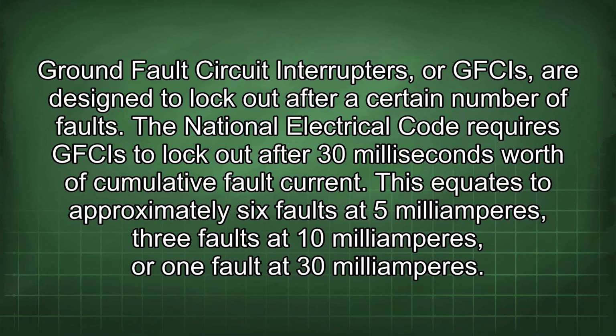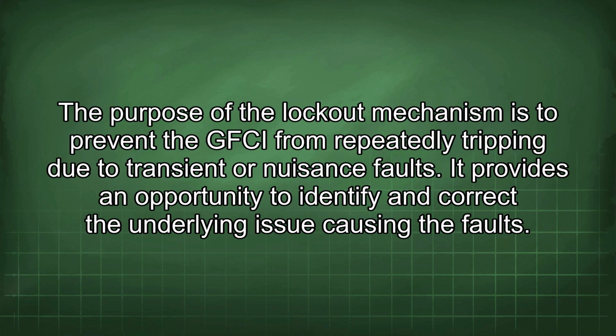Ground fault circuit interrupters, or GFCIs, are designed to lock out after a certain number of faults. The National Electrical Code requires GFCIs to lock out after 30 milliseconds worth of cumulative fault current. This equates to approximately 6 faults at 5 mA, 3 faults at 10 mA, or 1 fault at 30 mA. The purpose of the lockout mechanism is to prevent the GFCI from repeatedly tripping due to transient or nuisance faults. It provides an opportunity to identify and correct the underlying issue causing the faults.